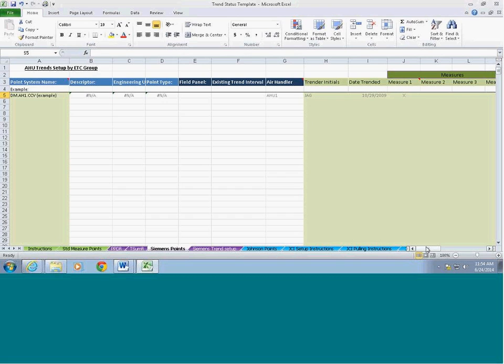Going back even further, if you go back to the scheduler, make sure both these reports are scheduled and coordinated, and that the trend data detail report has all the fields that are important, as we've already discussed. And then the trend collection report is really pulling it off that panel. So I just list 2 more on this, but this is the order that I'd recommend going backward. Try to be most efficient about this.